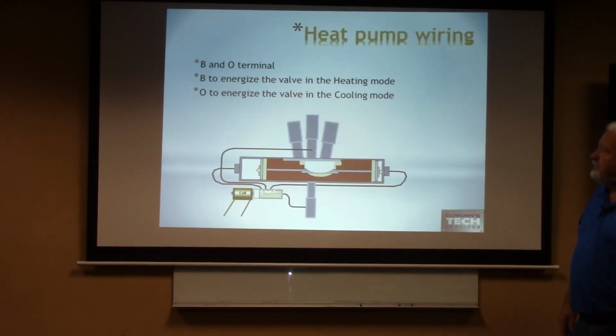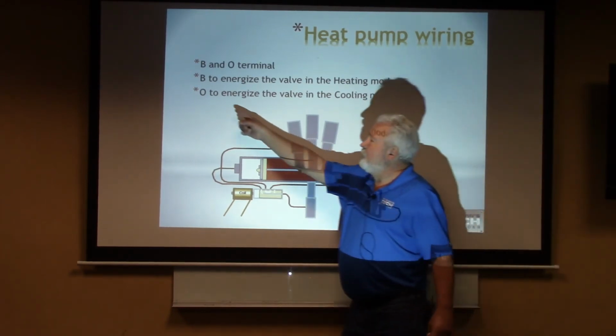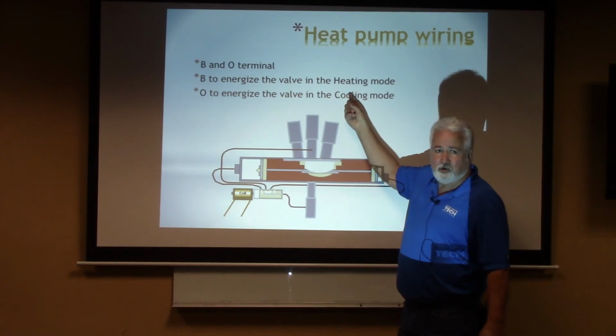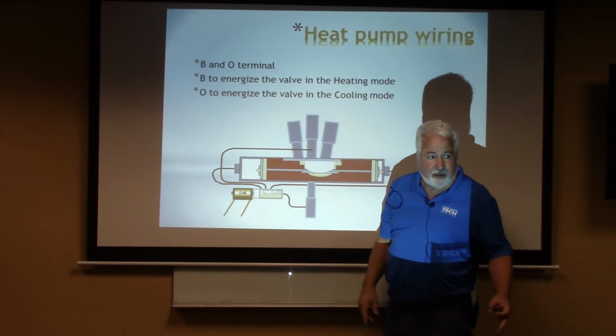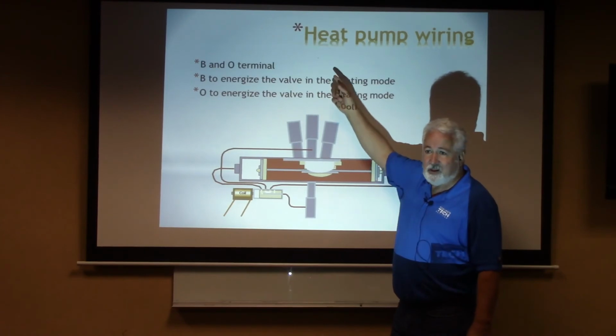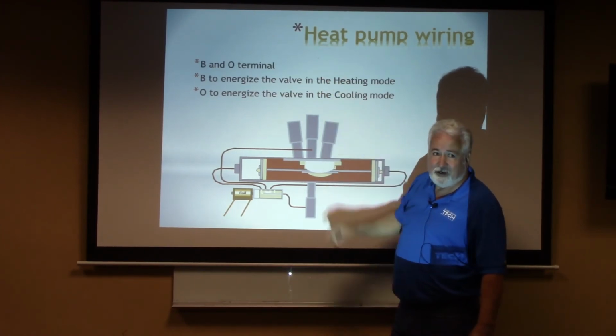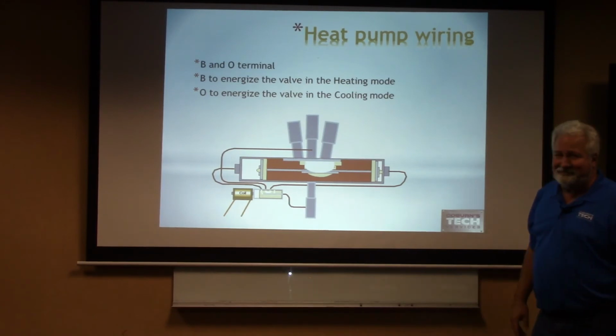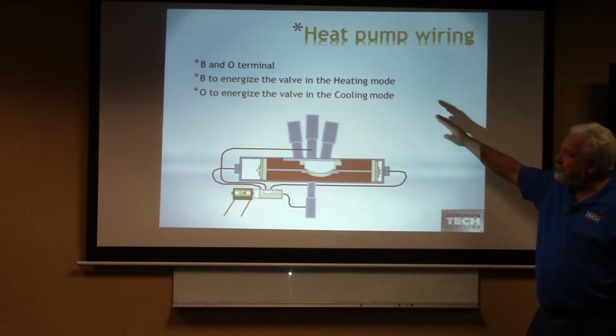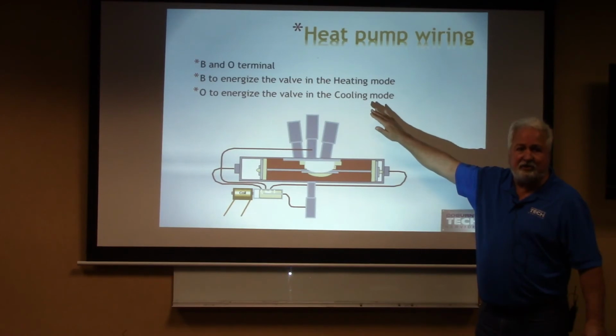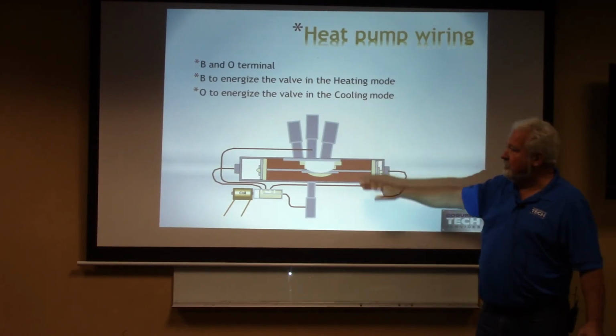All right, so if we're talking about a heat pump, I just wanted you to understand what that heat pump does. There's a B and an O terminal on your thermostat. The B energizes it in heating. The O energizes it in cooling. It's easy to remember. If you use the O, there's 2 O's in cooling. O, it energizes in cooling. The B for heating. All right. So we just understand that if you have the O terminal, you know it's going to energize in the cooling mode. Everybody okay with that? Good. So what does that mean?